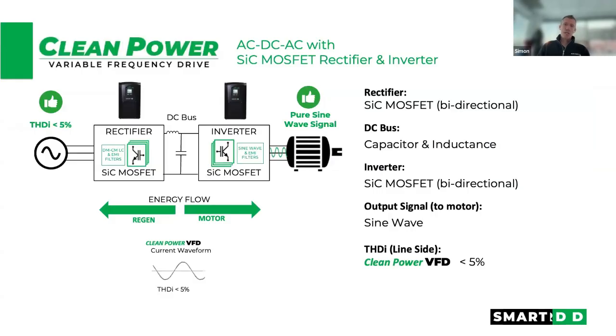And I mentioned it quickly, but our drive is also a fully 4-quadrant drive. So you're able to have full regen capability in the drive. You don't need a braking resistor. This is great on applications where you can benefit from this, where you really maximize your energy savings. And you also have that built-in DC bus so that you have that extra voltage boost on the output, and you have that protection from grid disturbance.